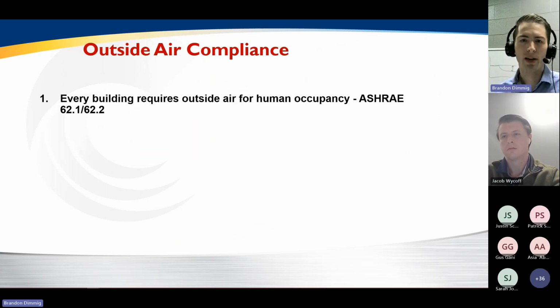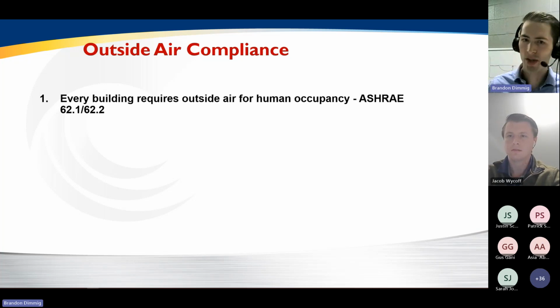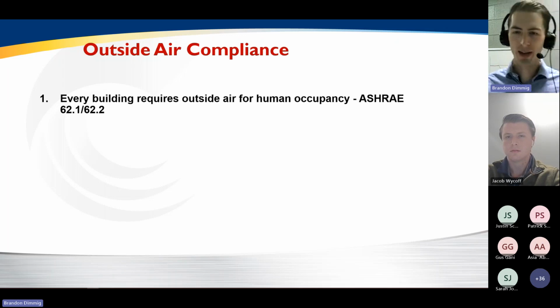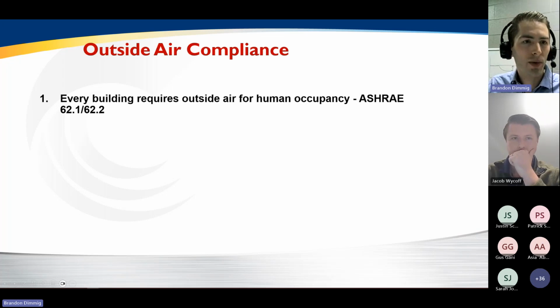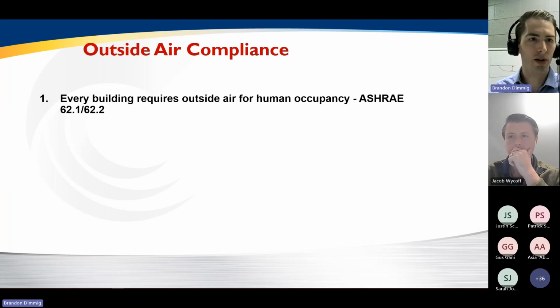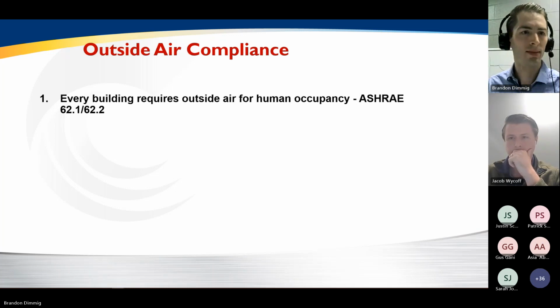So we know a couple things about outside air. One is that every building requires it for human occupancy. ASHRAE 62.1 is perhaps the best approach that we have to say what is an acceptable level for safe indoor air and how much outside air do we need. Let's do another raise of hands. How many of you all have done an ASHRAE 62.1 ventilation calculation in any of your projects? All right, I got at least 7 of you.